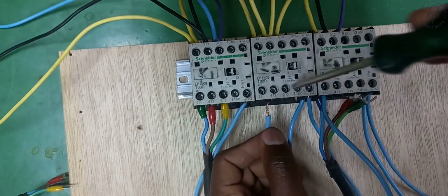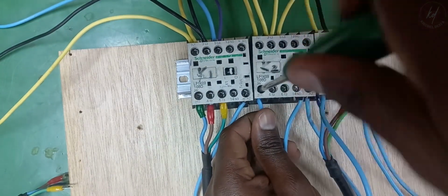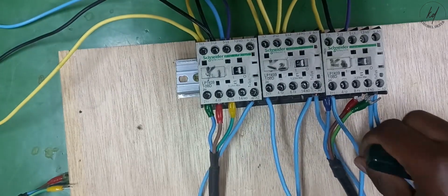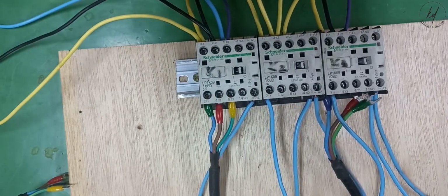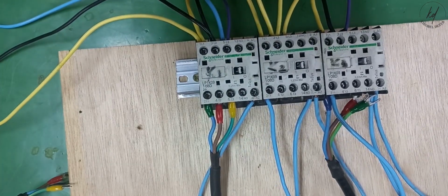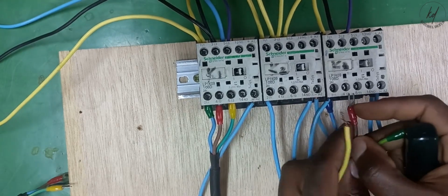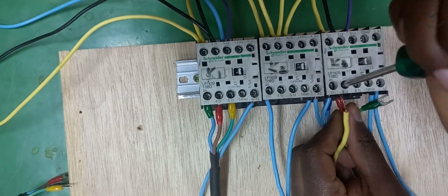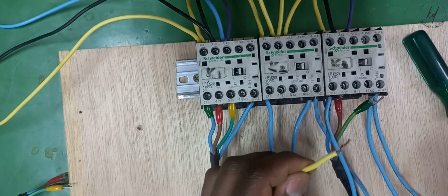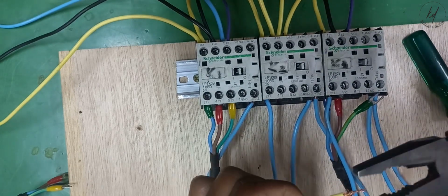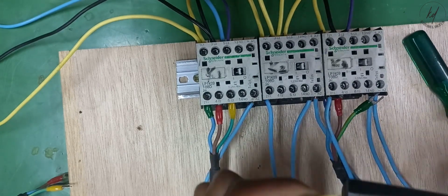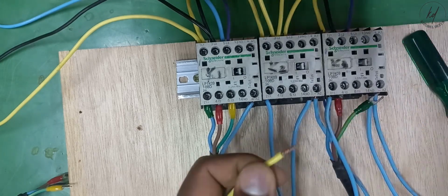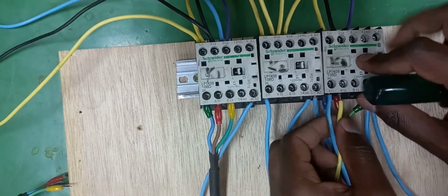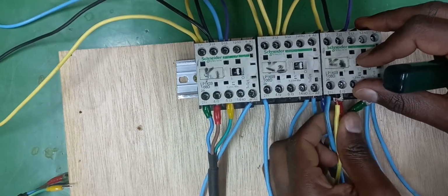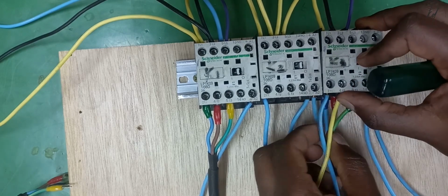Components used in the star-delta starters, mainly the contactor and thermal overload relay, are described as follows. A contactor is an electrical device which is used for switching an electrical circuit on or off. It is considered to be a special type of relay. However, the basic difference between the relay and contactor is that the contactor is used in applications with higher current carrying capacity, whereas the relay is used for lower current applications.